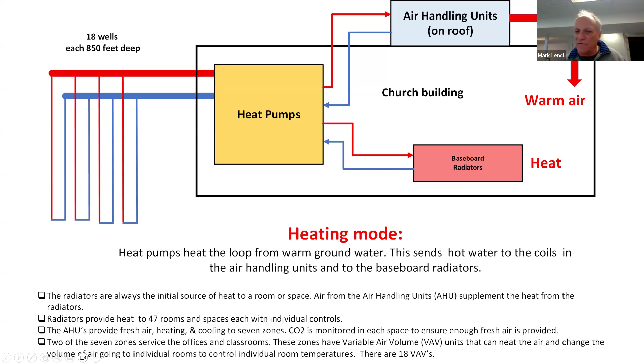In our situation, the radiators are always the initial source of heat. We keep these going in a hot water loop all the time, and there are 47 different zones, 47 different control valves. I'm just giving you these numbers to show the scope and complexity of balancing this all out. Then the air handling units provide air down to 7 zones. So that's the heating mode.